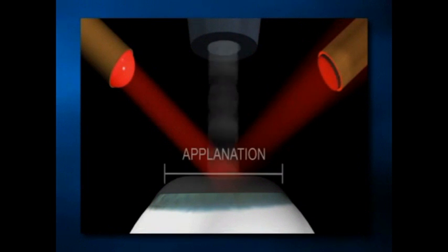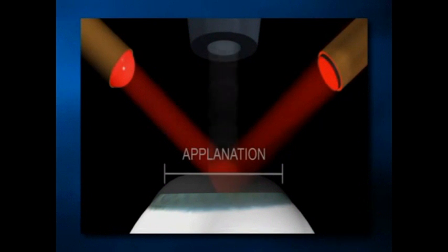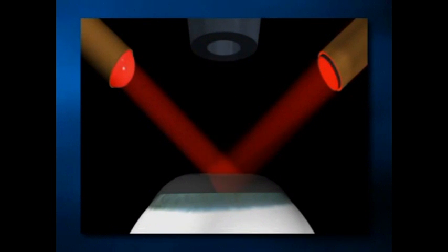As the velocity of the air pulse declines toward zero, the cornea returns to its natural shape and once again passes through an applanated state. The reflected light again reaches maximum intensity and causes a signal peak at the detector, triggering the pressure transducer to record the applanation pressure a second time. The cornea completely returns to its normal configuration and the sequence is concluded.